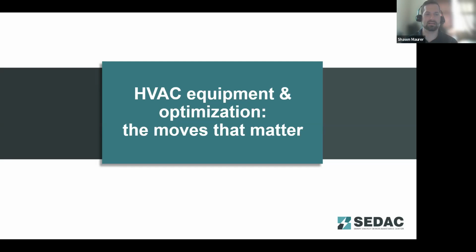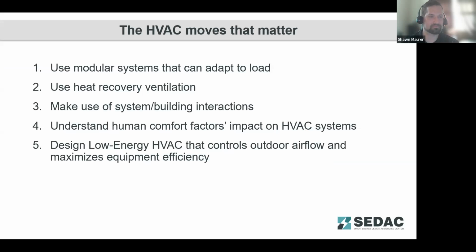Okay, so now let's take a look at HVAC equipment optimization and where to focus on those particular systems. One of the things that can really help with the efficiency overall of HVAC systems is use of modular systems that can adapt to loads. Variable speed fans, variable speed chillers, modular chiller systems where you've got a number of smaller units instead of a couple of really large units.